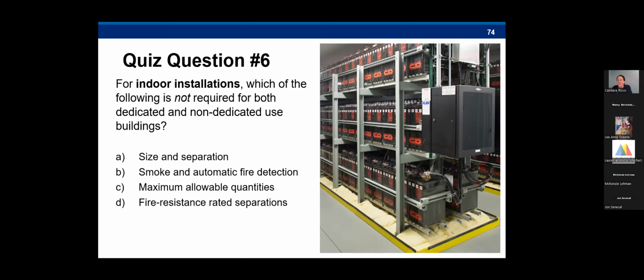All right, we got some answers in, but not the one I was hoping to see. So the answer here is C. Dedicated use buildings may exceed the maximum allowable quantities requirement. Both dedicated and non-dedicated use buildings still need to meet the size and separation, the smoke and automatic fire detection, and fire resistant rated separations. But for dedicated use buildings, they do not need to follow the maximum allowable quantities requirement.